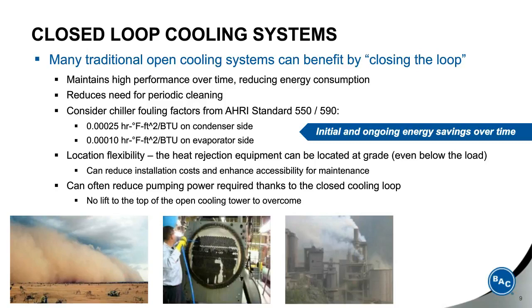With a closed loop, you have location flexibility. The heat rejection equipment can actually be located at grade or even below the load. You can reduce installation costs and enhance accessibility for maintenance. Another advantage is that the architects can use that location flexibility to help protect the aesthetics of the building in certain instances. You can often reduce the pumping power required thanks to the closed loop cooling. There's no need to deal with the lift required to the top of cooling towers on the open loop to overcome.